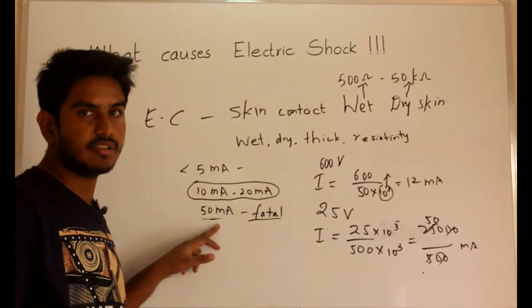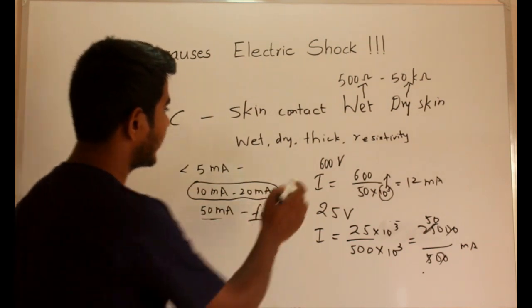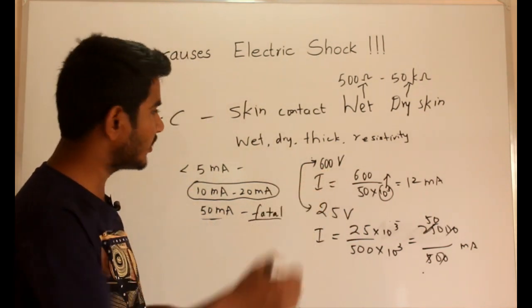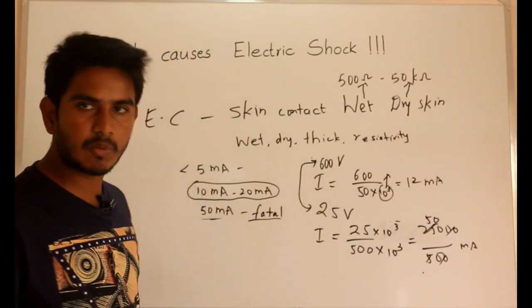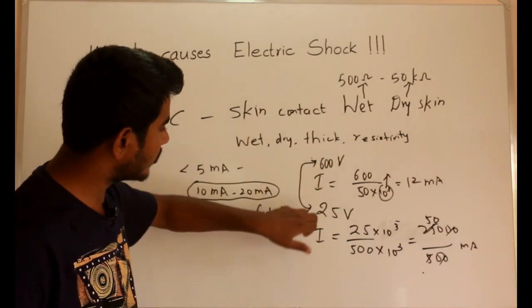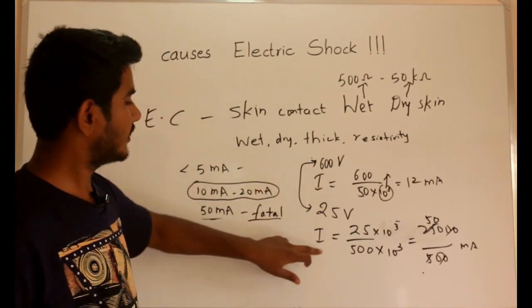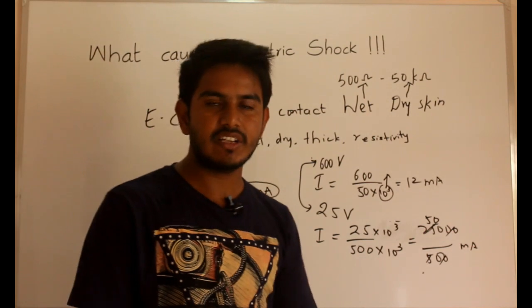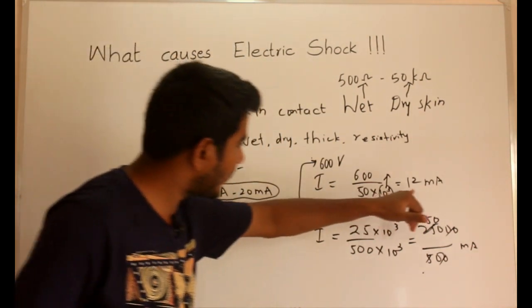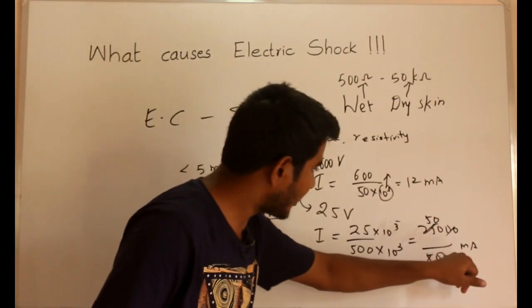So the current flowing through the body will be 50 milliamperes, and 50 milliamperes causes conditions to be fatal. This is why it is difficult to specify whether a voltage is dangerous or not. You can see that 600 volts versus 25 volts — you cannot specify which voltage is more dangerous. But the current tells you whether it is dangerous or fatal to the human body: 12 milliamperes is not fatal, but 50 milliamperes is fatal.